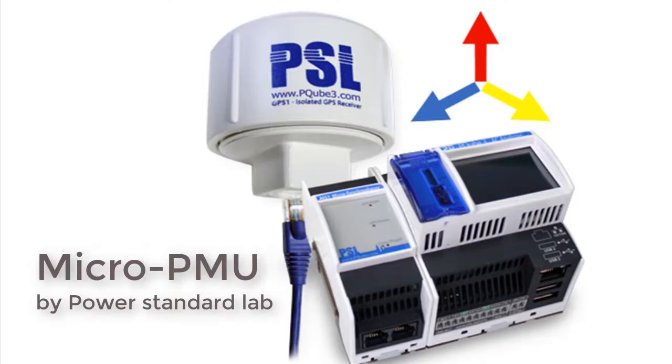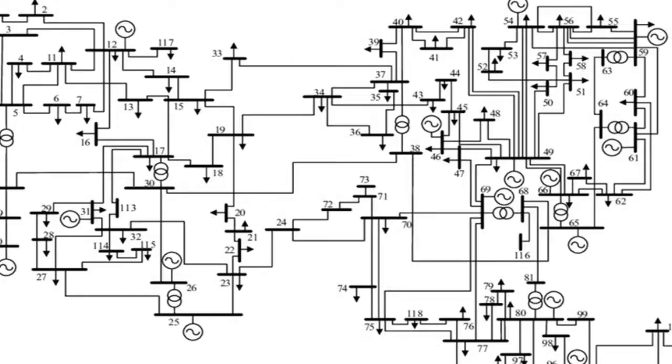Here, micro refers to the capability of a PMU to provide microscopic resolution of measurements. A general transmission PMU can publish at max 50 measurement reports per second, whereas micro-PMU can stream measurement reports at a rate of 100 or 200 measurement reports per second for a 50 Hz system.